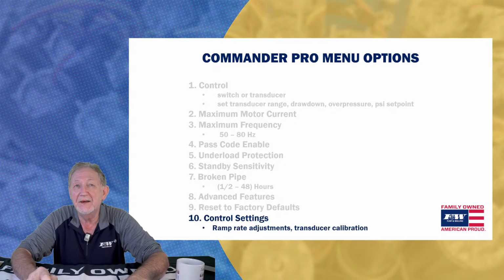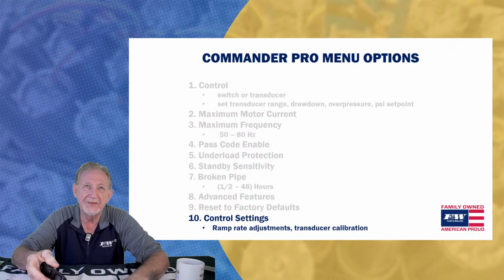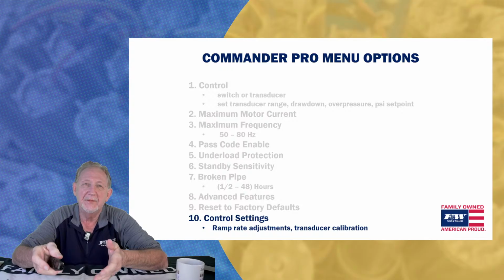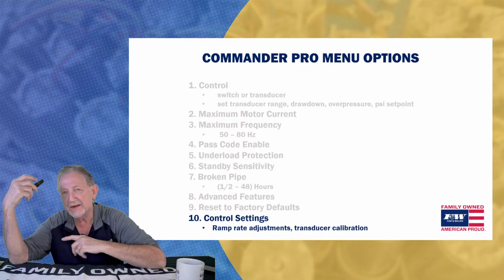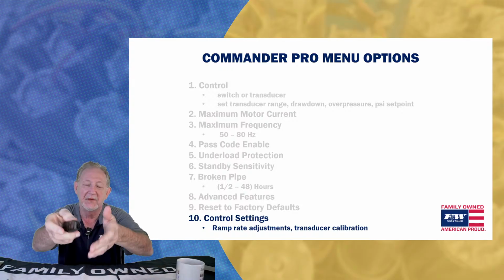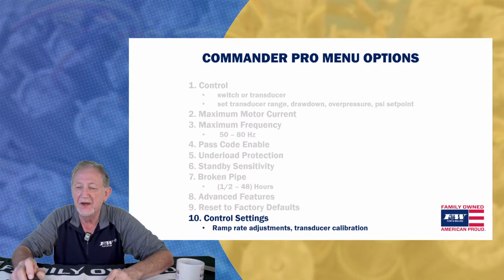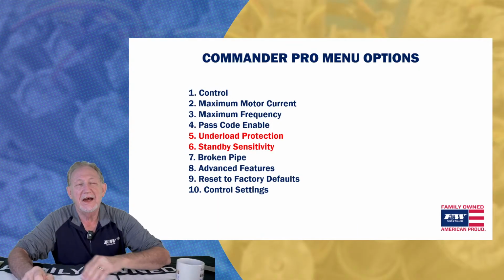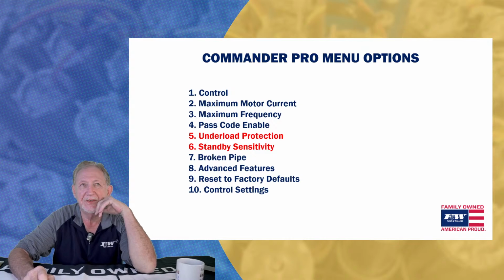Number 10 is control settings. Not often at all do we get in here. Very rarely, but those occasions where we do need to get in and adjust the ramp rates or calibrate the transducer, these are things that we're able to do that keeps that drive from having to come back to the factory, that can tweak it up for that particular job, all right? So let's look at these last, I'm going to finish this presentation off.